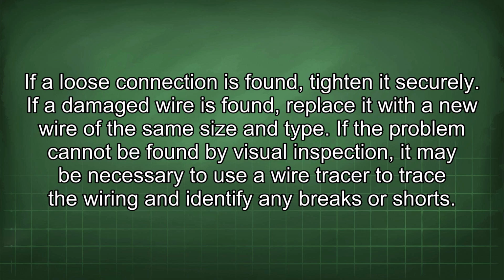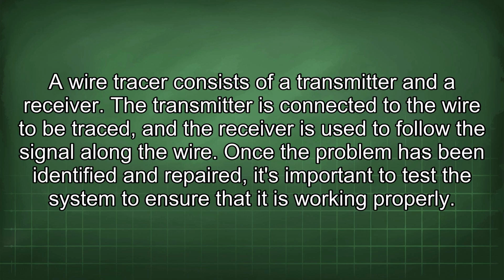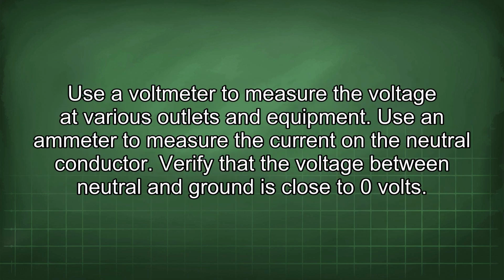Look for any signs of damage or loose connections. Check the neutral connections at the outlets, switches, and light fixtures. If a loose connection is found, tighten it securely. If a damaged wire is found, replace it with a new wire of the same size and type. If the problem cannot be found by visual inspection, it may be necessary to use a wire tracer to trace the wiring and identify any breaks or shorts.